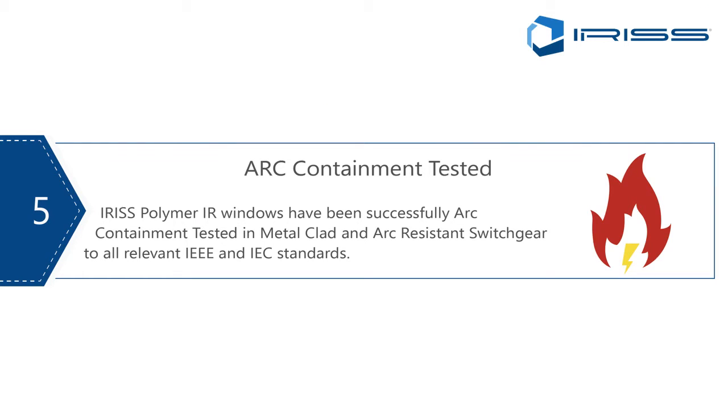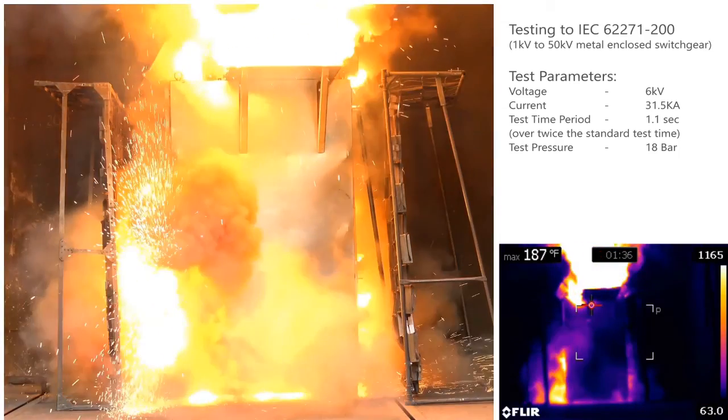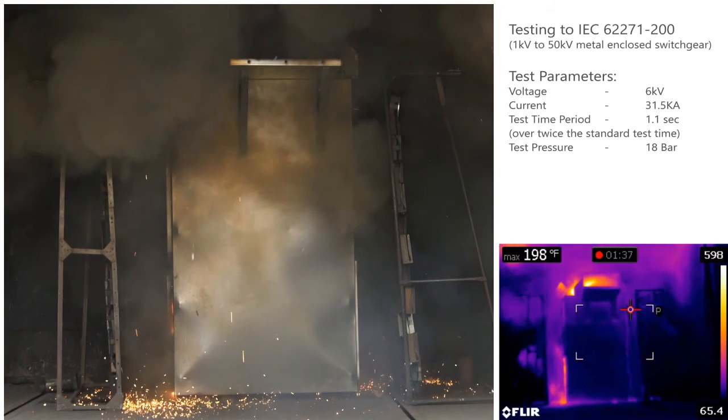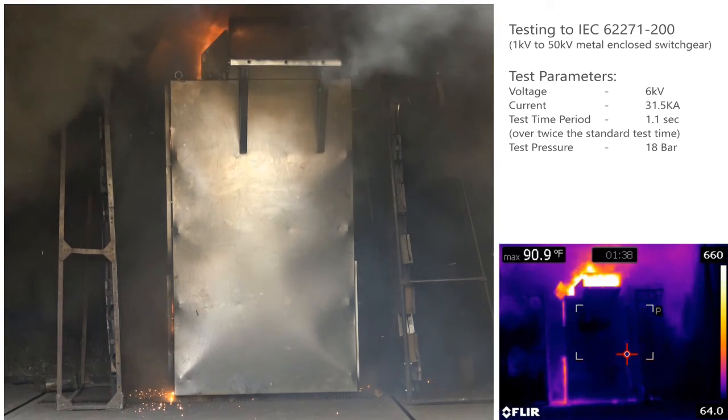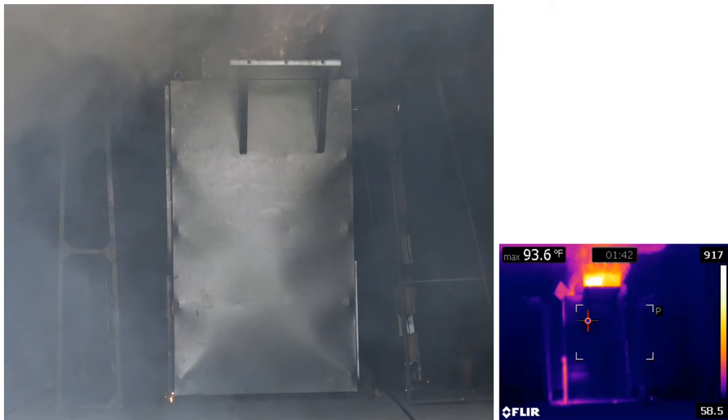Number five: ARC containment tested. There is a myth about ARC resistant windows — we do test infrared windows continuously with OEMs in their systems to define their ARC containment properties. At IRISS we came up with a test required on metal clad switchgear, which is a much tougher test. The test shown here was conducted to IEC 62271-200, which covers 1 kV to 50 kV metal enclosed switchgear — specifically a 6.5 kV, 31.5 kA test with pressures of about 18 bar, a test period of 1.1 seconds, and a peak current of 83 kA. The new EMV systems were designed to beat that.